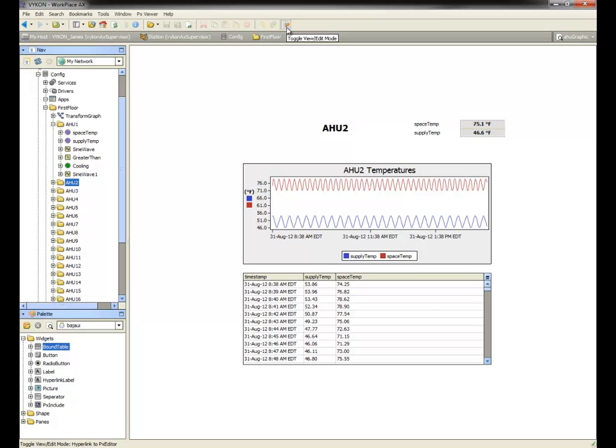The data sources are histories and can be referenced by the actual history ORD, or they can leverage B format syntax, which is resolved against the base component of the PX view when the chart or table widget is displayed. Using the B format syntax in the source ORD property allows a single transform graph to be used in a relative PX view, which may be assigned to any number of identical devices in the station. This provides robust reporting capabilities while minimizing the required engineering effort.